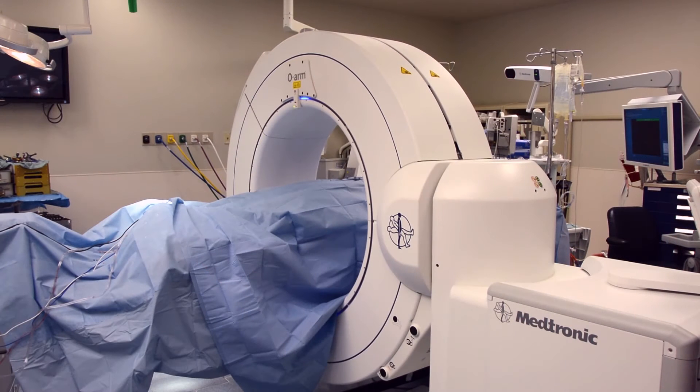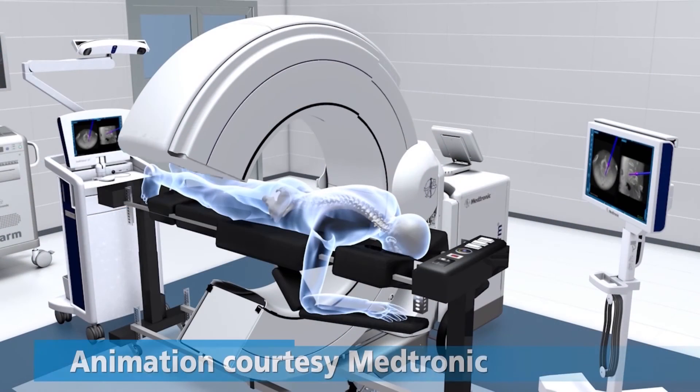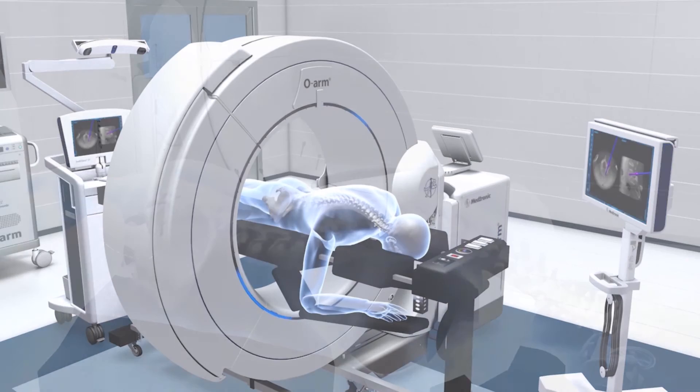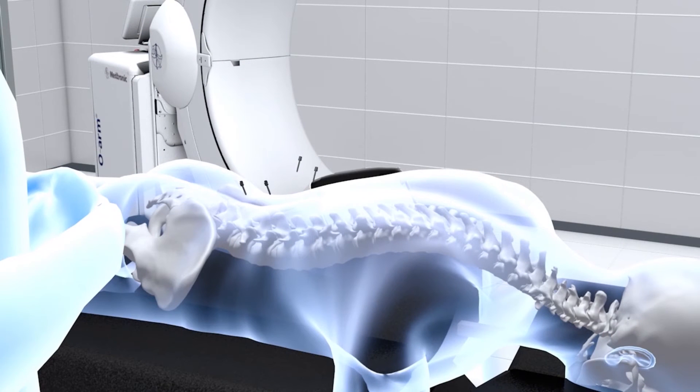The O-arm is a portable imaging device that forms a ring around the patient's body. It rotates to perform a 15 to 20-second scan that generates a 3D computer model of the patient's spine. During surgery, these images provide real-time confirmation of the location of the surgical tools and implants to within a millimeter's accuracy.